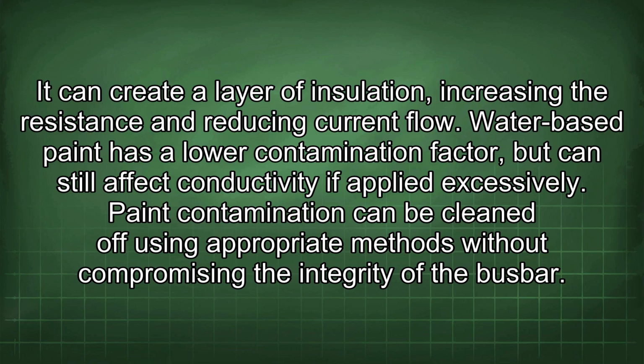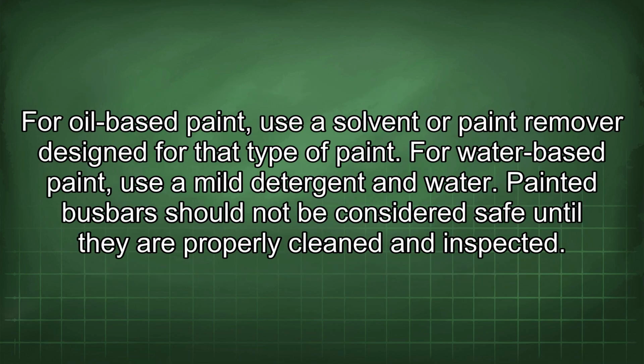Water-based paint has a lower contamination factor, but can still affect conductivity if applied excessively. Paint contamination can be cleaned off using appropriate methods without compromising the integrity of the busbar. For oil-based paint, use a solvent or paint remover designed for that type of paint. For water-based paint, use a mild detergent and water.